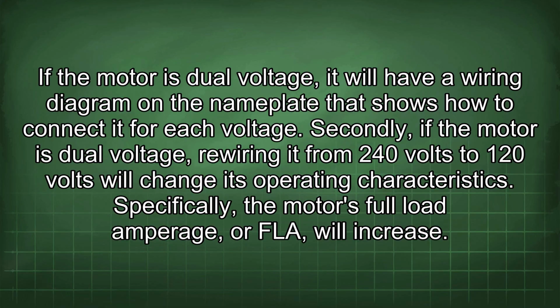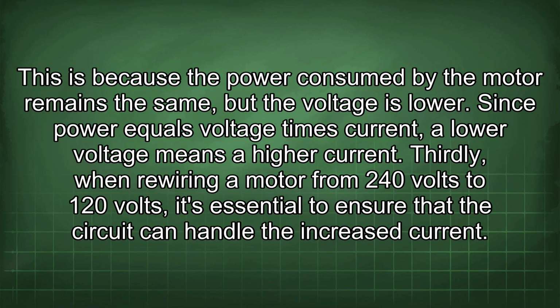Secondly, if the motor is dual voltage, rewiring it from 240 volts to 120 volts will change its operating characteristics. Specifically, the motor's full load amperage, or FLA, will increase. This is because the power consumed by the motor remains the same, but the voltage is lower. Since power equals voltage times current, a lower voltage means a higher current.